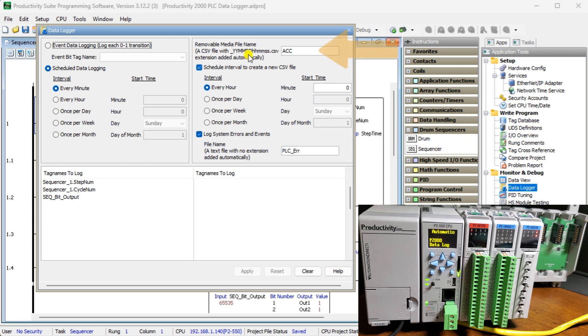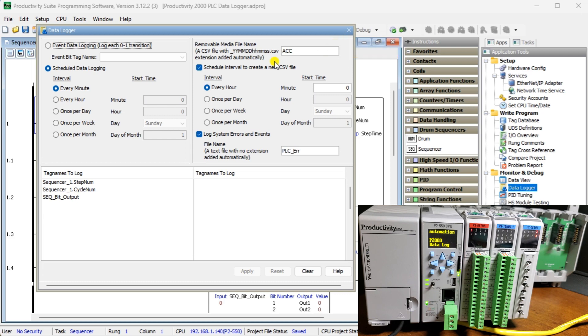Removable media file name: enter the prefix of the file name for the USB device. The name entered will always be appended by dash MMDDHHMM.csv, where the time and date reflect the CPU time and date for the first entry. The CPU will create a logs folder and save the log file on the USB storage device. The schedule interval to create a new CSV file means the name will be the same but with a new date and timestamp.